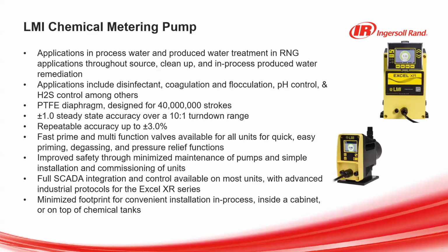If we go to the next slide, some of the applications that you might see in RNG are primarily related to processed water and produced water, and treating that water out of that RNG applications from source to cleanup and in-process remediation. Applications primarily in terms of chemicals that are being pumped through these include disinfectant chemicals, coagulants and flocculants, such as different types of polymers, water and oil-based polymers, pH control, and H2S control, among many other applications where chemistry balancing is required in order to produce the RNG gas, and then also to be able to remediate water that's produced out of this process.